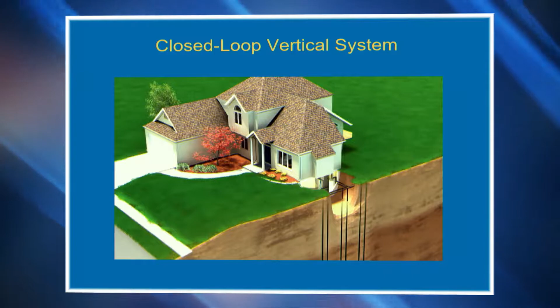This is a picture of a vertical ground loop system. We'll drill a well, install a pipe in the well, bentonite and graphite it, then heat fuse the pipes together and bring them into the building - that's where the heat transfer comes from. We're taking the delta from 50 degrees and transferring it into your house at 70. That's why it's more efficient - you're not using air at 0 degrees to heat the house, you're using the ground at 50 degrees.